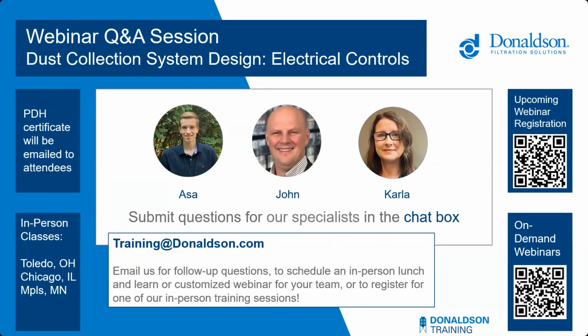That is a good question. It is determined by the environmental hazards, obviously, but if a dust hazard analysis, or DHA, is conducted, oftentimes the company providing the DHA will include some analysis on the hazardous zones. Otherwise, it is kind of up to the process owner and the person specifying to ensure that the hazardous zone is accurate. If you need assistance with this, I know our sales team frequently will go out to sites to determine what the hazardous zones are and what is appropriate to spec out for an electrical installation, but it's not a one-size-fits-all answer.